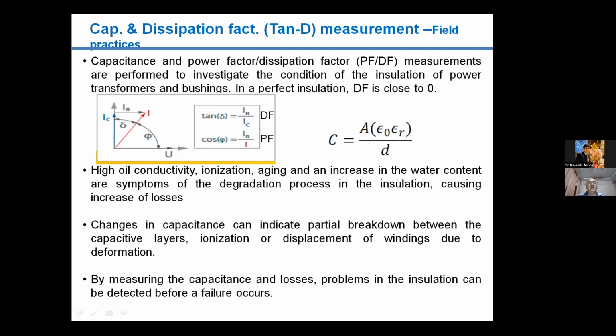When you do this test, generally we discuss two terms, power factor and dissipation factor. Many times, when these factors reach towards zero value, both are almost equal. Otherwise, the two are different. One is tan delta and the other is cosine. One is tan and the other is cosine. Both are indicated here in the picture.